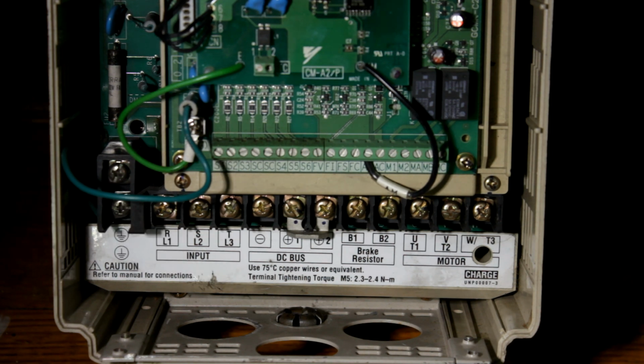Now notice there's a jumper between 1 and 2, and they both say positive. If you were to remove that jumper, that's where a DC choke goes, or an inductor. It's really just there to improve the power factor and reduce noise fed back into the grid from the variable frequency drive. So with this type of drive, and most modern motor controllers, both the control power and the power for the main inverter come from the same source, and that is the DC bus.